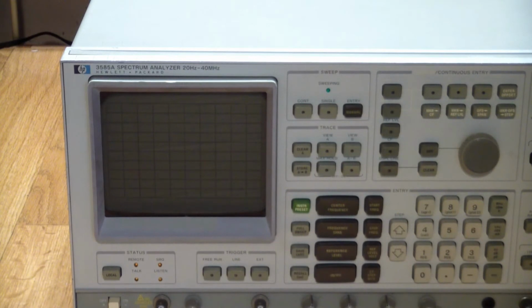Now, sitting that long in a closet, probably a good percentage of all the electrolytic capacitors in here are going to drift. The drifts are going to be different and unpredictable. So what I'm getting at is that to do this properly, we would have to go in and do a manual calibration of it. But I'm not going to do that right now. I'm just bringing this up because our results are going to be somewhat falsified because of the lack of calibration. Second of all, the function generator I'm going to use is also out of calibration, so the cumulative error is also going to affect the signals that we see. But with that in mind, let's go and give it a signal.